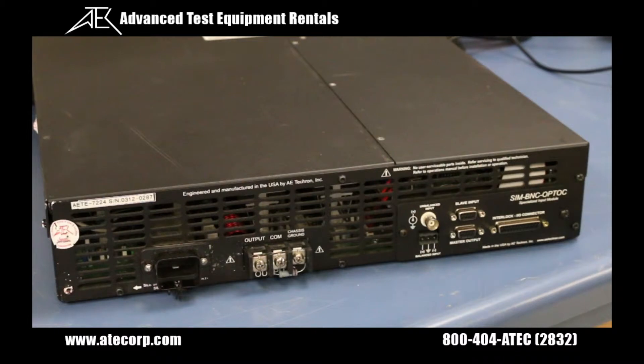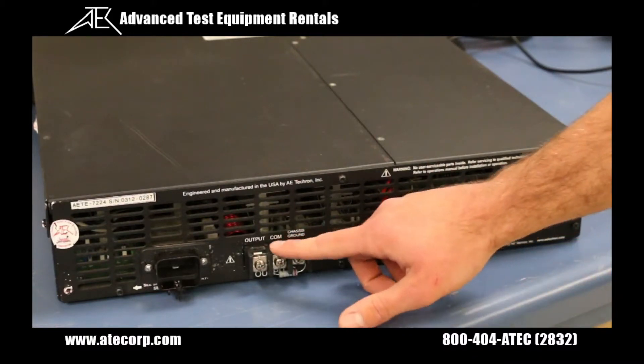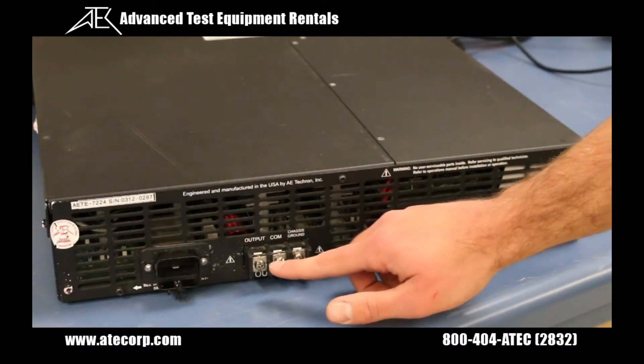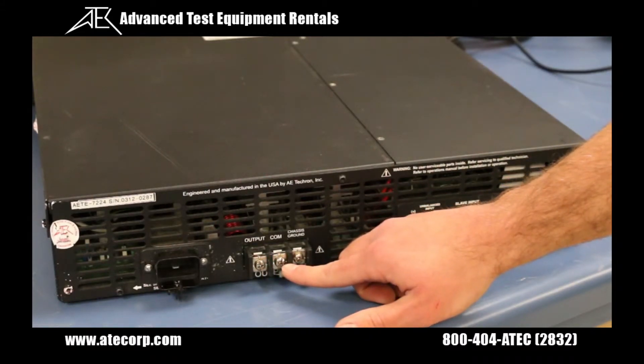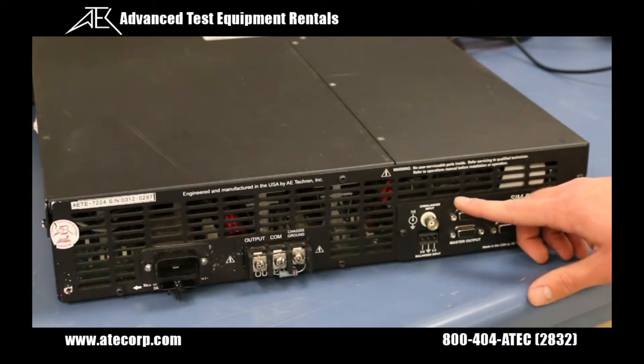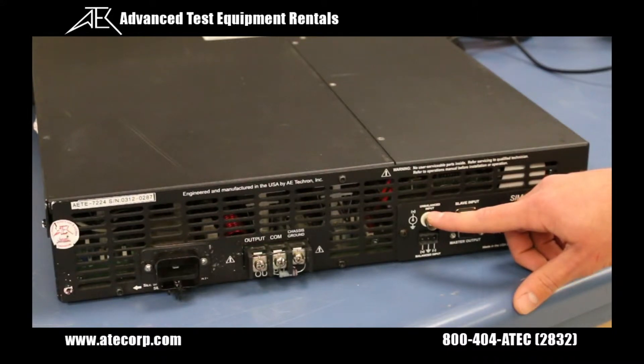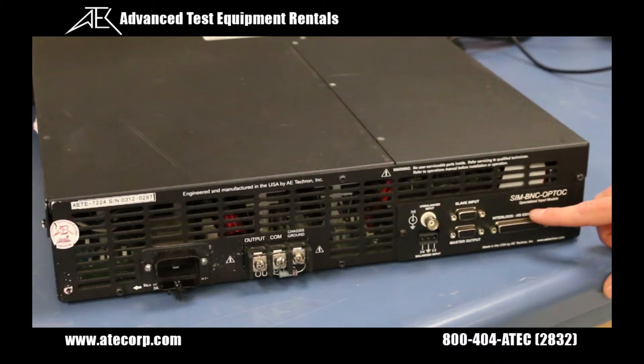Next we have our back panel connections. We have your standard 20 amp 60 Hertz 3-pin AC input connector. Here we have the amplifier output terminals which are where we will connect our load. The load will be connected across the output and com terminals and our chassis ground can be connected to any external ground point. Our input signal is applied through the SIM BNC OPTOC panel. We have both an unbalanced BNC input and a balanced input terminal block to choose from. The interlock connector can be used to provide remote control and monitoring of the amp, allowing you to remotely enable or place the unit in standby, as well as monitor both the voltage and current output. It also allows you to monitor one or more amplifier conditions including run status, over temp, overload, and over voltage.